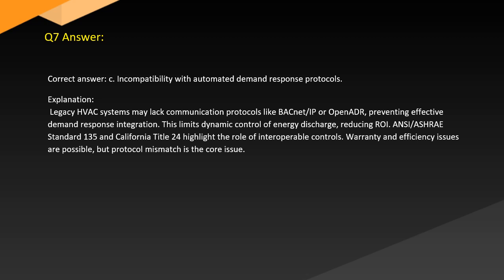Answer. Correct answer: C. Incompatibility with automated demand response protocols. Explanation. Legacy HVAC systems may lack communication protocols like BACnet/IP or OpenADR, preventing effective demand response integration. This limits dynamic control of energy discharge, reducing ROI. ASHRAE Standard 135 and California Title 24 highlight the role of interoperable controls. Warranty and efficiency issues are possible, but protocol mismatch is the core issue.